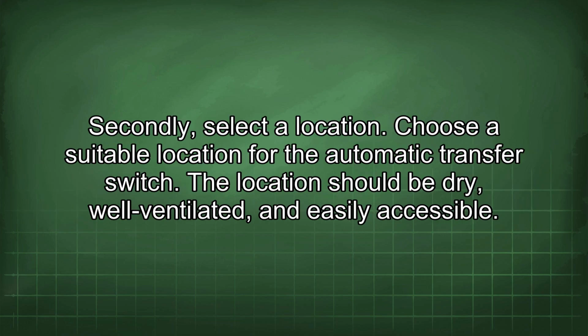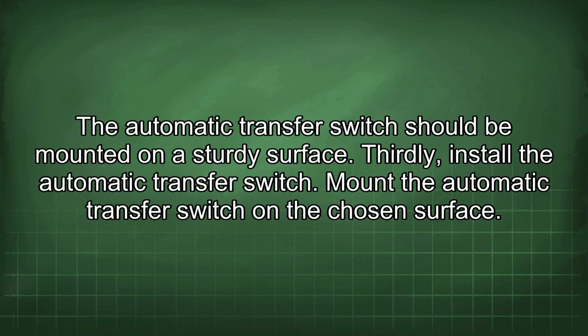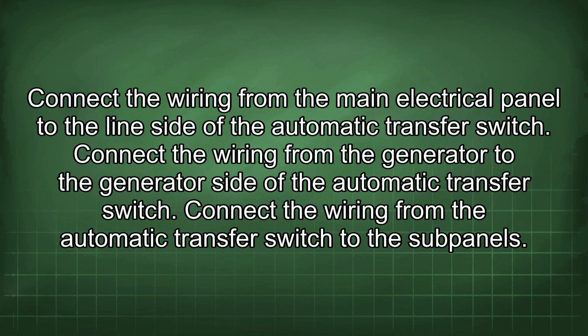Secondly, select a location. Choose a suitable location for the automatic transfer switch. The location should be dry, well ventilated, and easily accessible. The automatic transfer switch should be mounted on a sturdy surface. Thirdly, install the automatic transfer switch. Mount the automatic transfer switch on the chosen surface. Connect the wiring from the main electrical panel to the line side of the automatic transfer switch. Connect the wiring from the generator to the generator side of the automatic transfer switch. Connect the wiring from the automatic transfer switch to the subpanels.